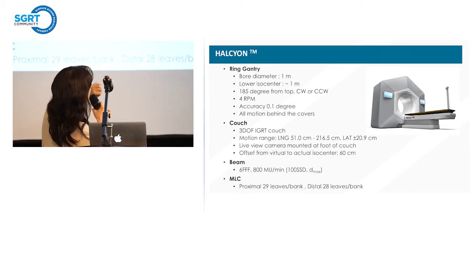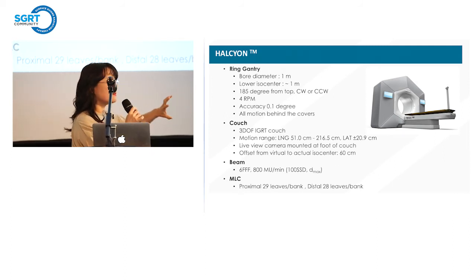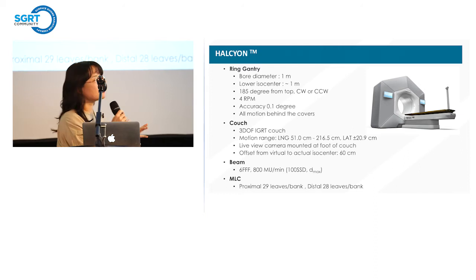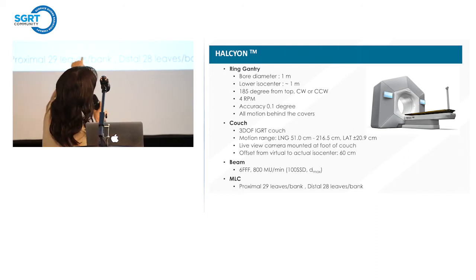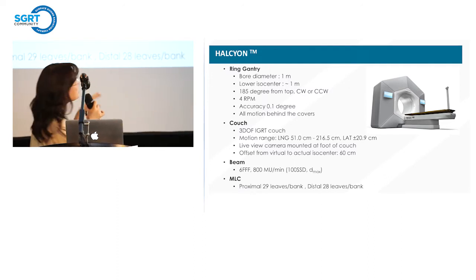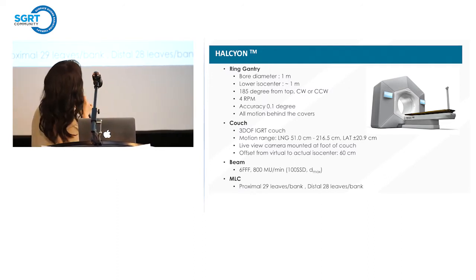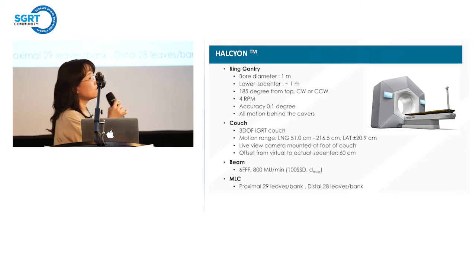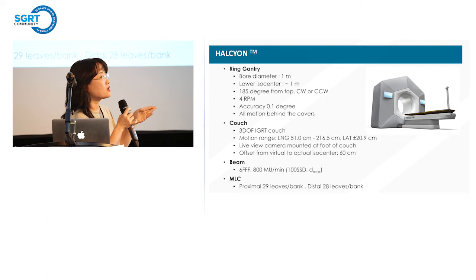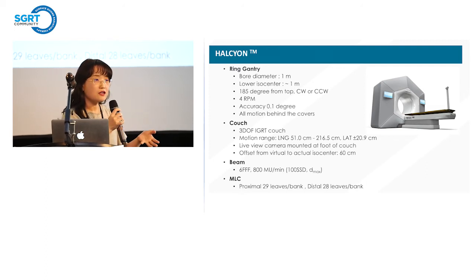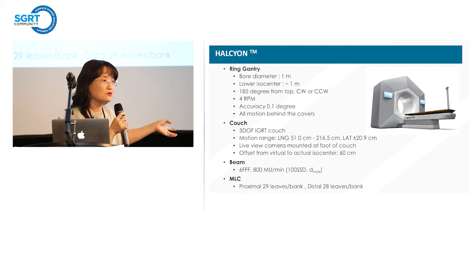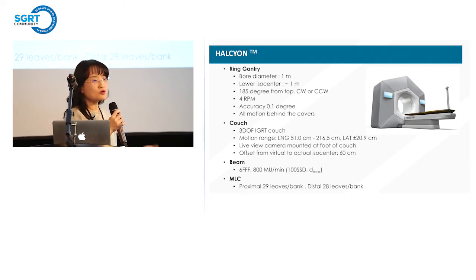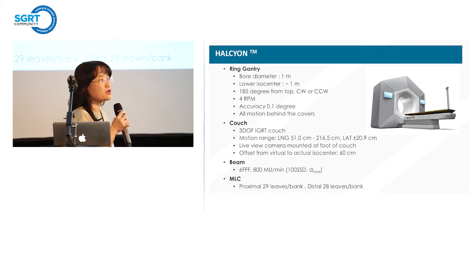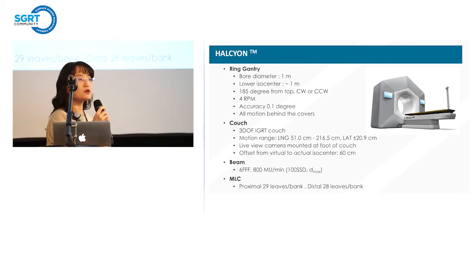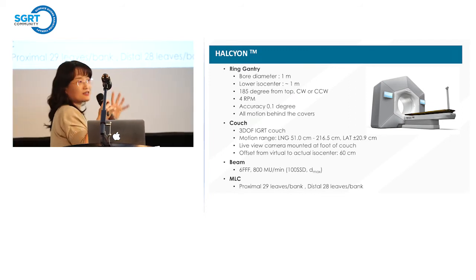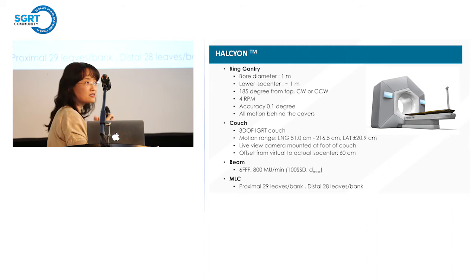But it has a lot of good features in terms of couch tracking, and the MPC tracks all the details about the couch and isocenter information. There's also a live view camera mounted at the end of the couch to keep monitoring the patient. Then there's a virtual ISO. There is some laser set, and the virtual ISO exists, the same as in your CT scanner, and the real ISO is invisible. So basically there are no field lights, no crosshair, nothing there. You cannot see the isocenter, and there's no way to check the ODI. That's very fantastic, but at the same time it's a little bit of a blind spot as a physicist.